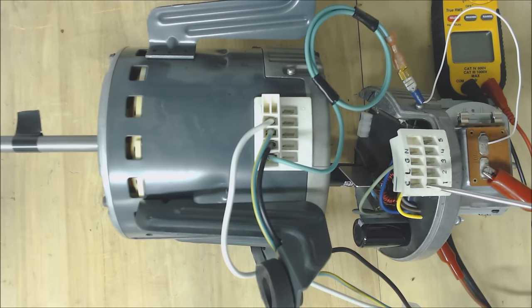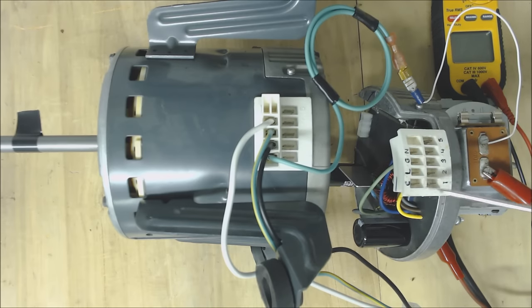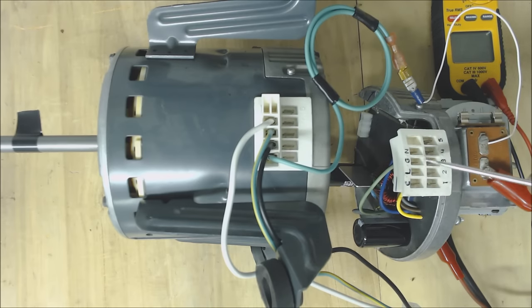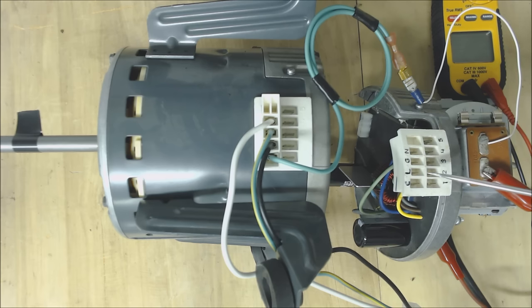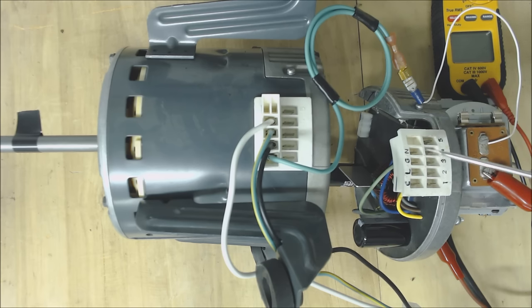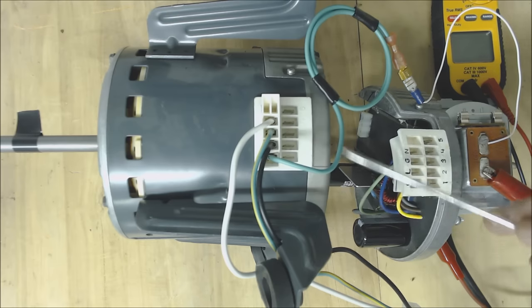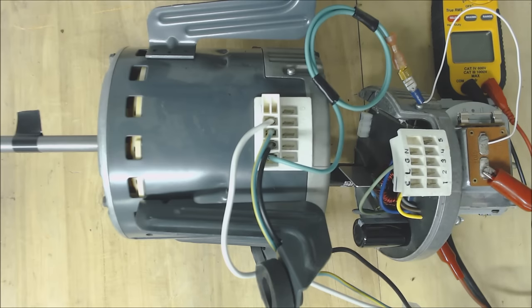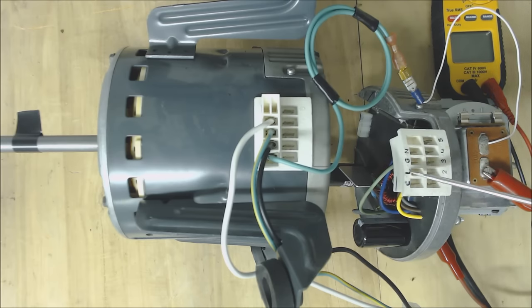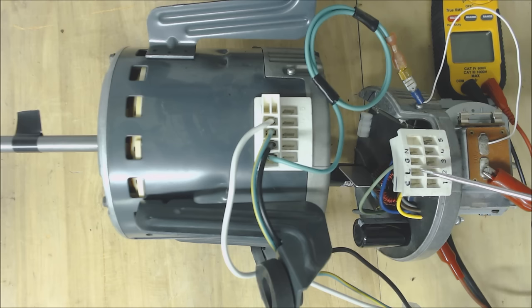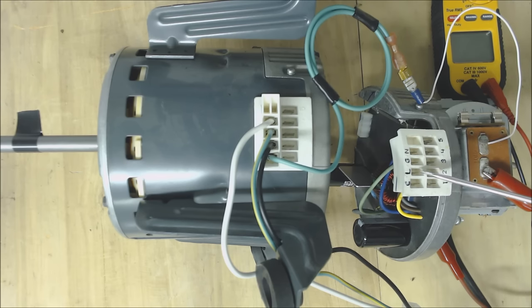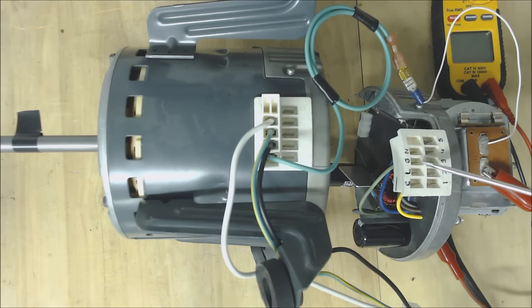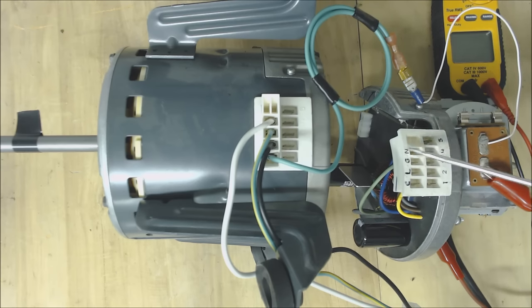It's important to note that this right here is your 24 volt common. The rest of these taps up here are for your high voltage either 120 volts or 240 volts as stated on the rating plate of the X13 blower motor. So this right here is L for line so if you had 120 volt furnace powering this then this was your 120 volt hot. This is your ground G for ground and then N for neutral or common.